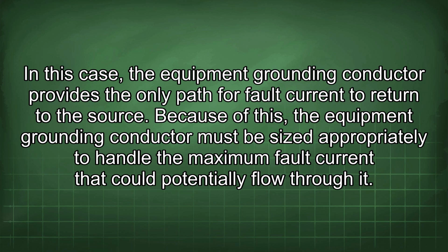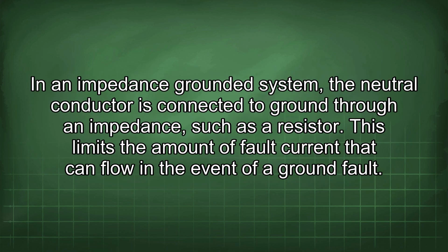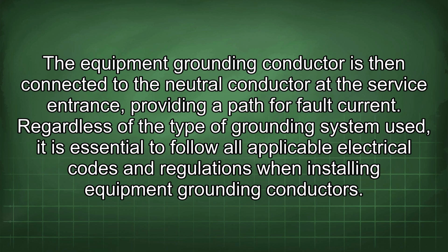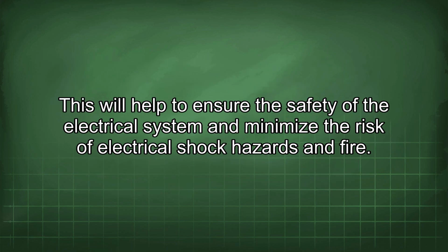Because of this, the equipment grounding conductor must be sized appropriately to handle the maximum fault current that could potentially flow through it. In an impedance-grounded system, the neutral conductor is connected to ground through an impedance such as a resistor. This limits the amount of fault current that can flow in the event of a ground fault. The equipment grounding conductor is then connected to the neutral conductor at the service entrance, providing a path for fault current. Regardless of the type of grounding system used, it is essential to follow all applicable electrical codes and regulations when installing equipment grounding conductors.